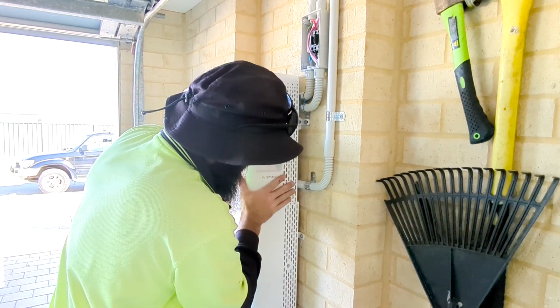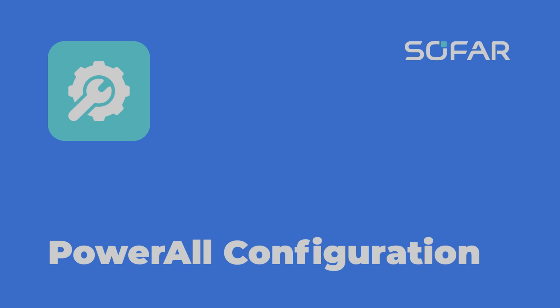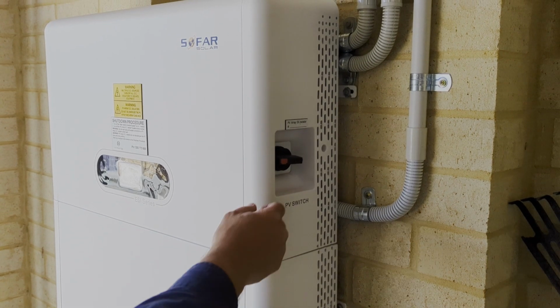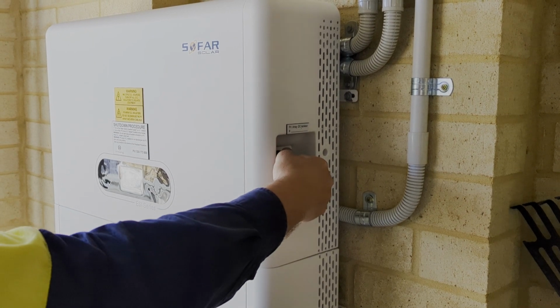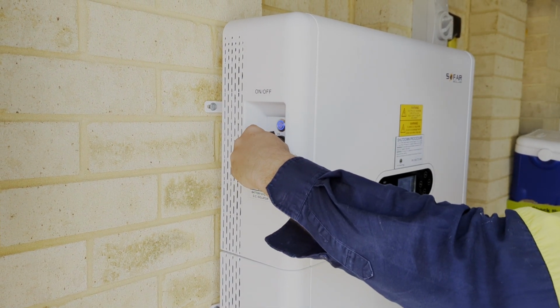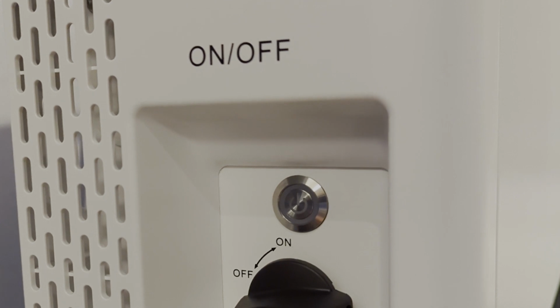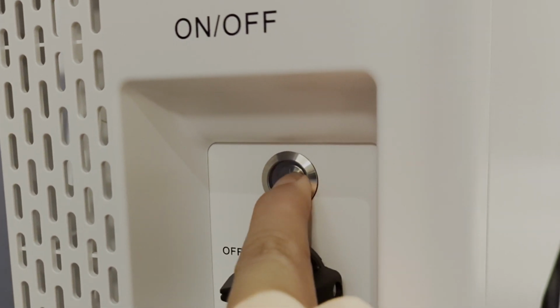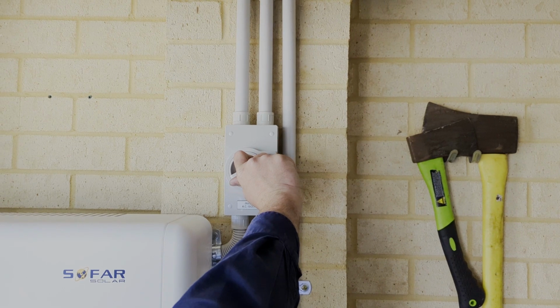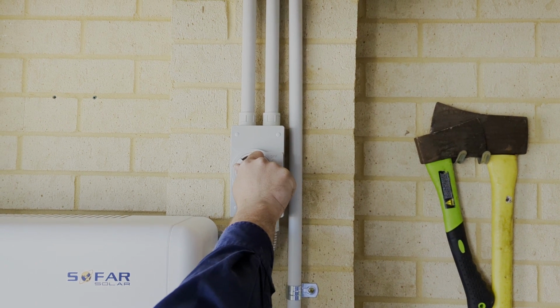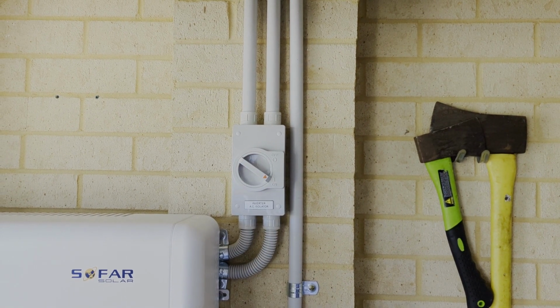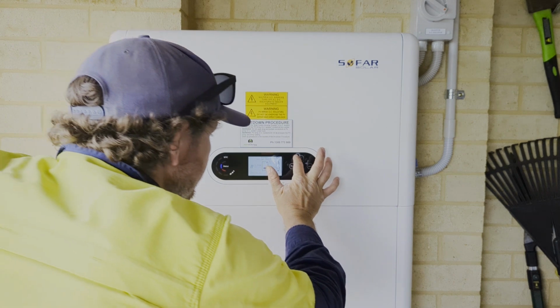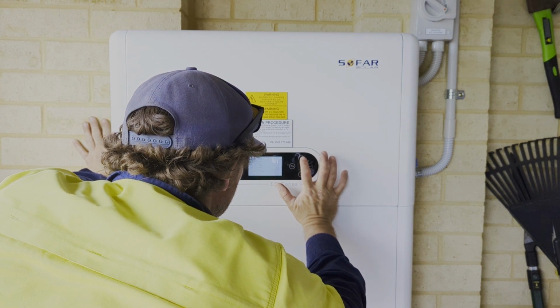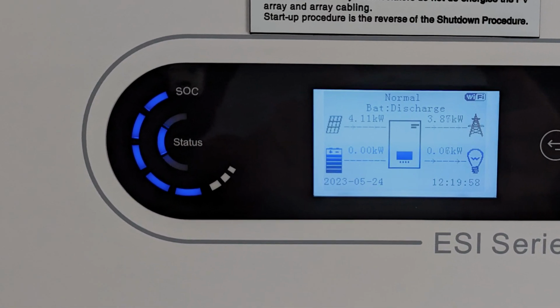With the system fully wired, the covers can be attached and screwed in place, and you can move on to the commissioning. Switch the DC switch on the PV side of the product to on. Switch the DC switch on the battery side of the product to on, and press the battery black start button to activate the battery. Finally, turn on the AC circuit breaker between the inverter power grid port and the power grid. Press the system button and the inverter starts running. The system status indicator is blue.